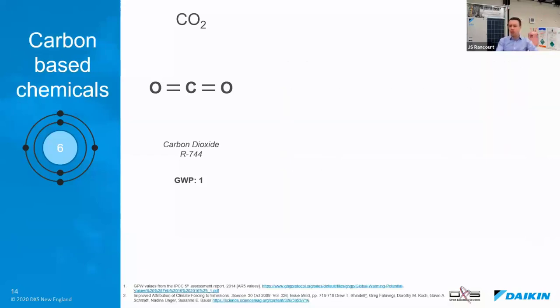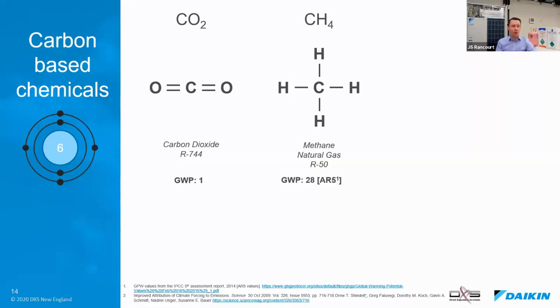Let's continue with other common carbon-based chemicals. This one is called methane. You might be familiar with it. This is what it looks like. Again, 4 connections, 1 to each hydrogen atom. This is methane. It's also known as natural gas. Natural gas, as you know of today, is essentially pure methane. It's also known as R50. Methane is a refrigerant, or could be. Now, for obvious reason, we don't use it as a refrigerant because it's a fuel. It's highly flammable. It also doesn't have the thermodynamic properties that we may want. Methane has a GWP of around 28, according to the 5th assessment of the IPCC.